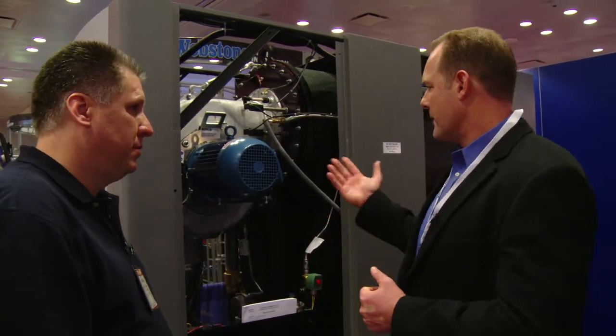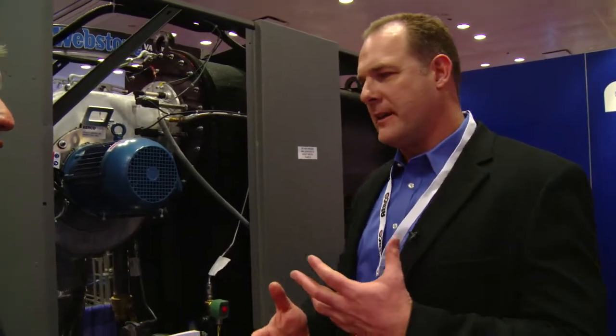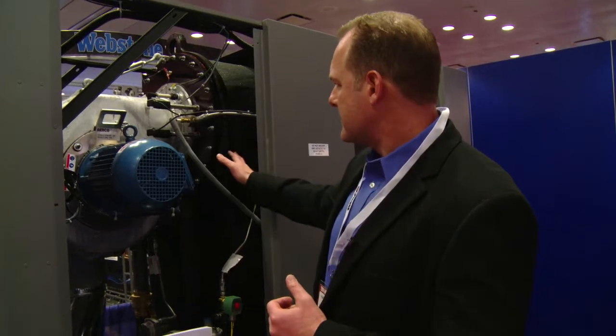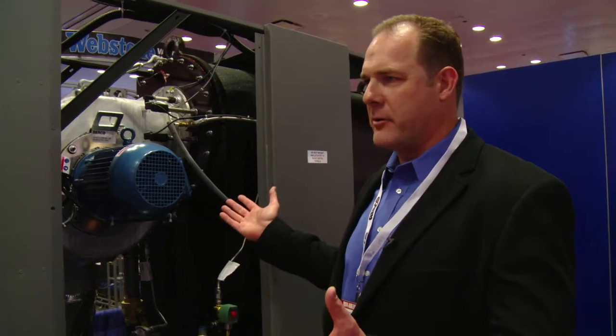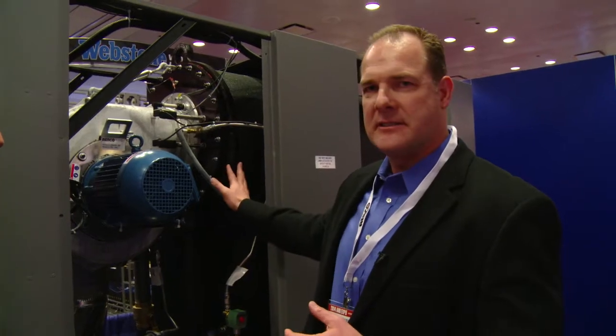We work on a lot of high-efficiency equipment. A lot of them have a heat exchanger with a high pressure drop requiring specialty pumps. Tell me about the pressure drop on this heat exchanger. Well, when you're talking about the pump side, you're talking about the water side. So as far as being capable of varying flow, which is very common in today's industry where everybody wants to use variable flow drives on their pumps, this heat exchanger, because it's a fire tube design, can be applied in a primary variable flow application. So a customer can take not only advantage of the thermal efficiencies of the boiler, but also the pumping and energy savings on the pump by varying the flow in the system and across the heat exchanger with very low pressure drops. Very nice, very nice.